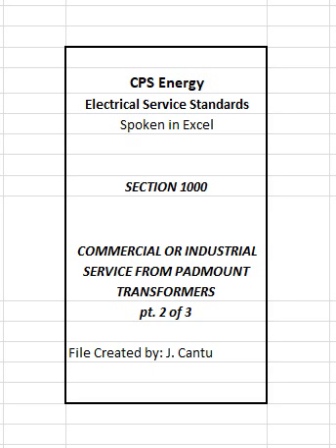To schedule an inspection, customer may contact the CPS Energy customer service representative or refer to helpful numbers listed on the inside front cover page. Note: CPS Energy reserves the right to require customer to remove any or all of the concrete and surrounding fill to expose reinforcing steel, footings, etc. when a slab inspection was not obtained prior to it being poured. D. Transformer installation. Access to transformer slab by crane, equipment, and personnel must be free and clear of obstructions and debris. Transformer slab must cure for a minimum of 72 hours prior to installation of transformer.